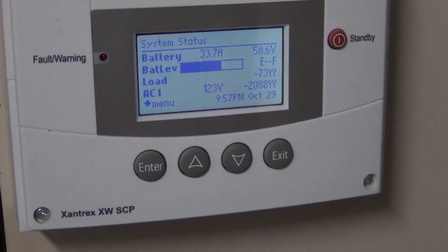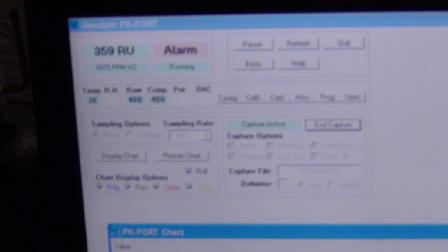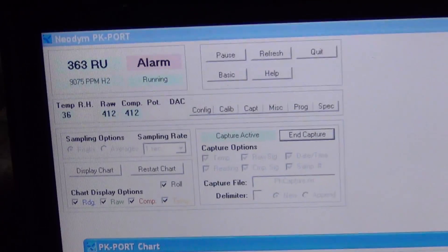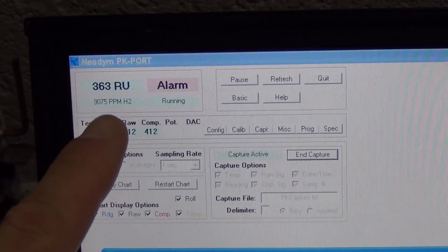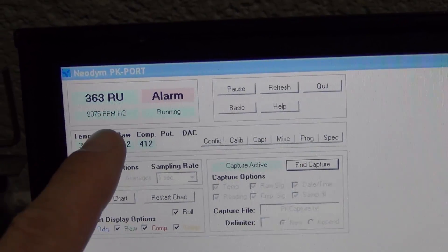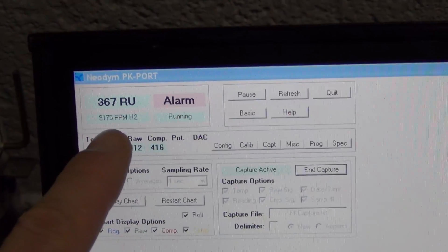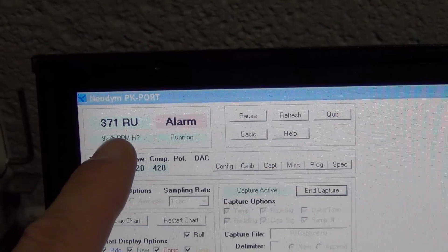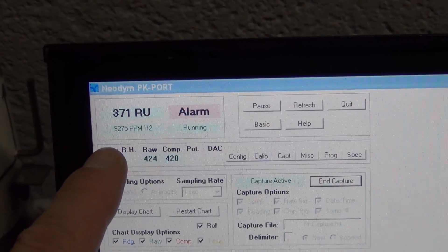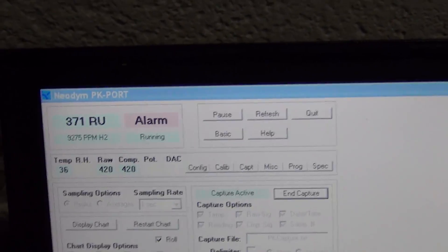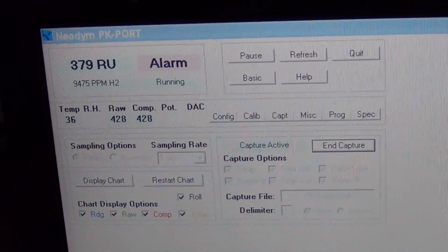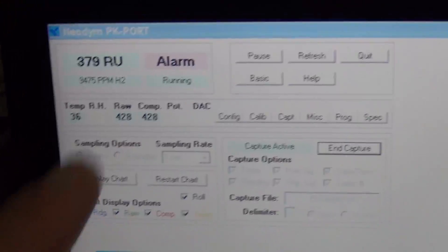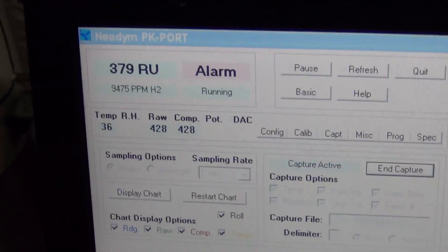But now you hear something in the background, which is a beeping sound. And what that is, is the Hydronose sensor. The Hydronose sensor is set for once this gets above 8,000, which is 0.8% of ratio with air. And right now we're at 9,293. It's starting to really climb. And the concern is when this hits 40,000, which is still quite a ways away. We just have the alarm set pretty low here.